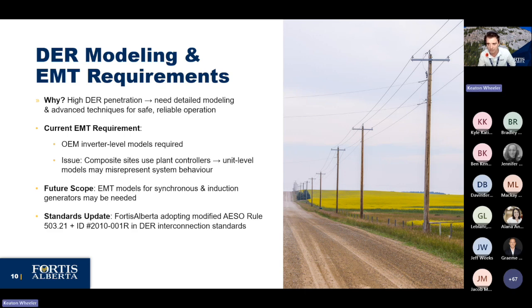For sites where electromagnetic transient models are required, current requirements for inverter-based resources ask for unit-level OEM models of the specific inverter. The issue is that when dealing with composite sites, everything 500 kVA and above, that employ power plant controllers, they affect the performance and behavior of the DER plant. So system level studies with a unit level model may be inaccurate, which may lead to unnecessary mitigations.